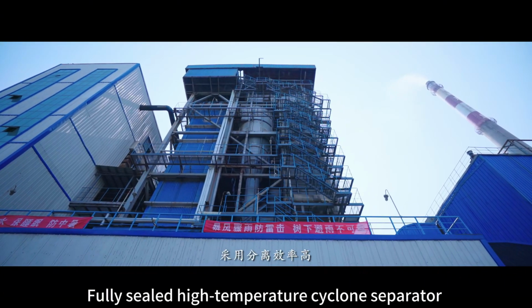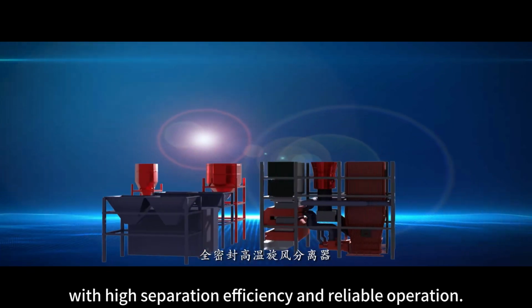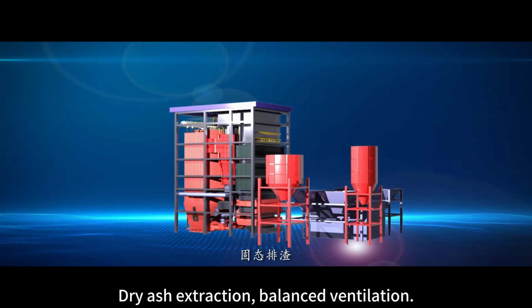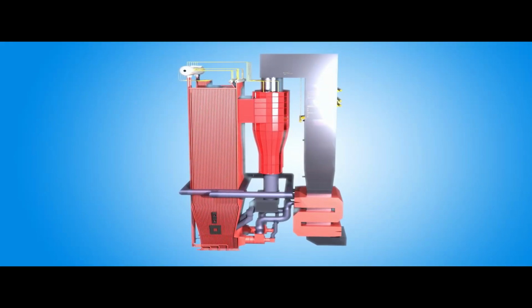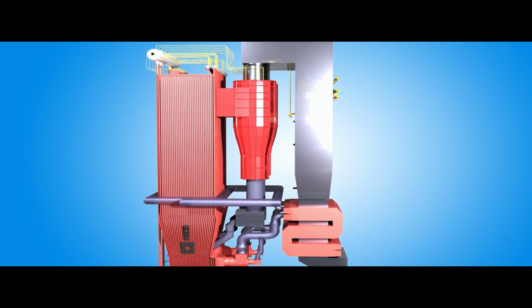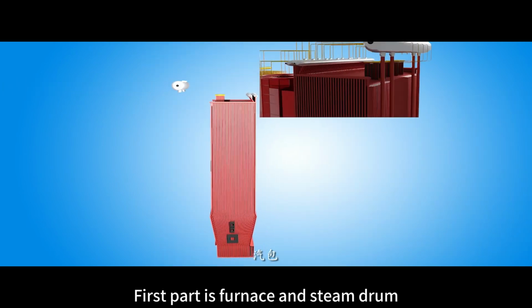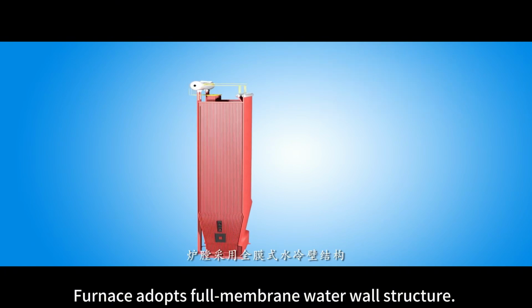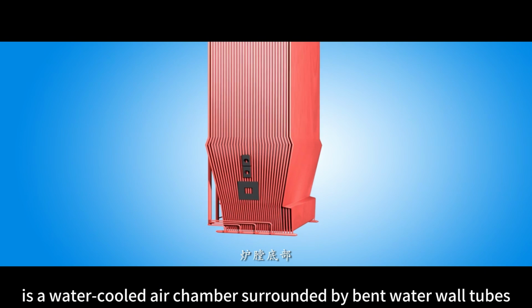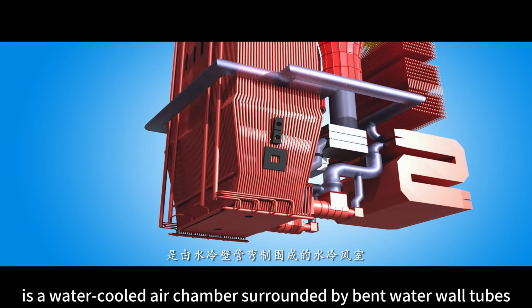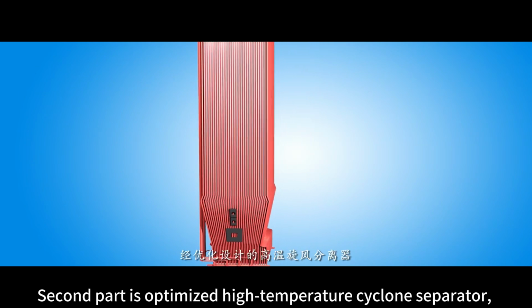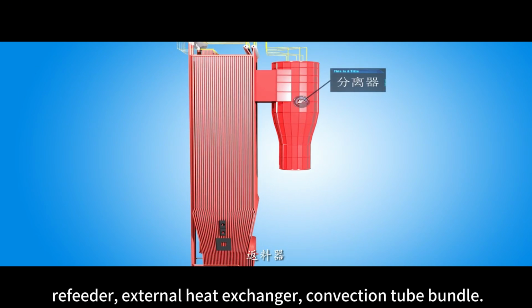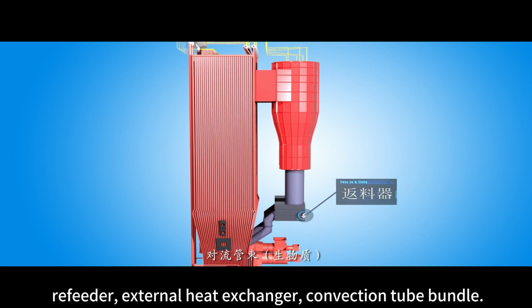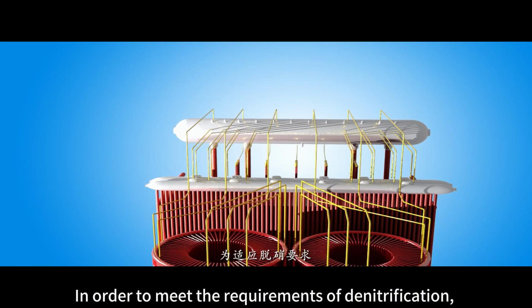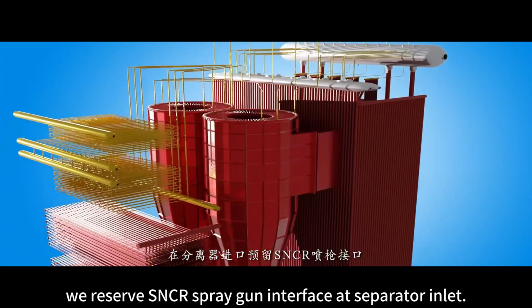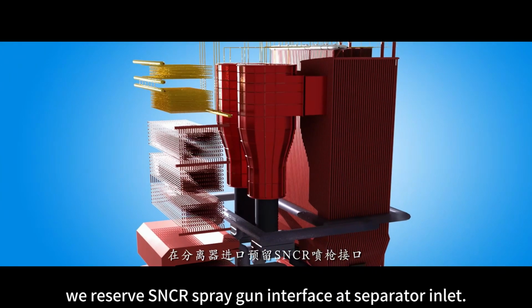Fully sealed high-temperature cyclone separator with high separation efficiency and reliable operation. Dry ash extraction, balanced ventilation. Boiler depth is generally divided into three parts. First part is furnace and steam drum. Furnace adopts full membrane water wall structure. Bottom is a water-cooled air chamber surrounded by bent water wall tubes. Second part is optimized high-temperature cyclone separator, refeeder, external heat exchanger, convection tube bundle. In order to meet the requirements of denitrification, we reserve SNCR spray gun interface at separator inlet.